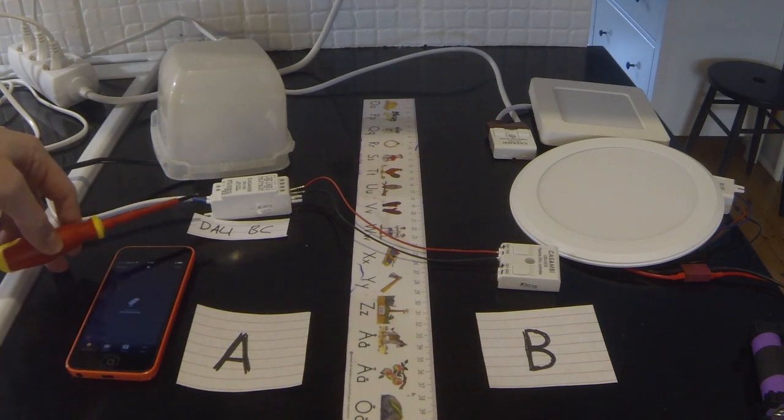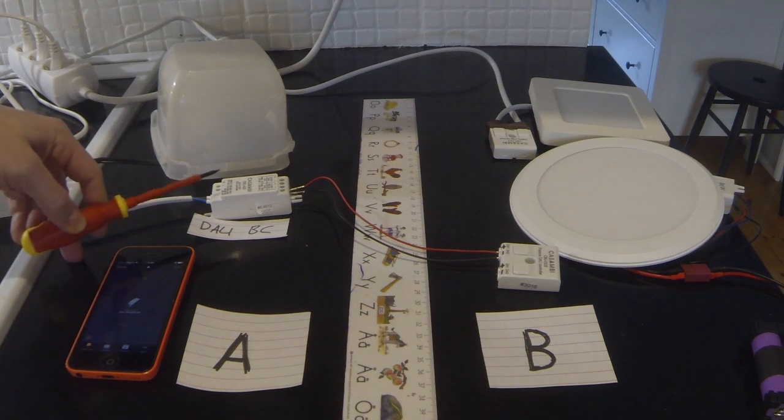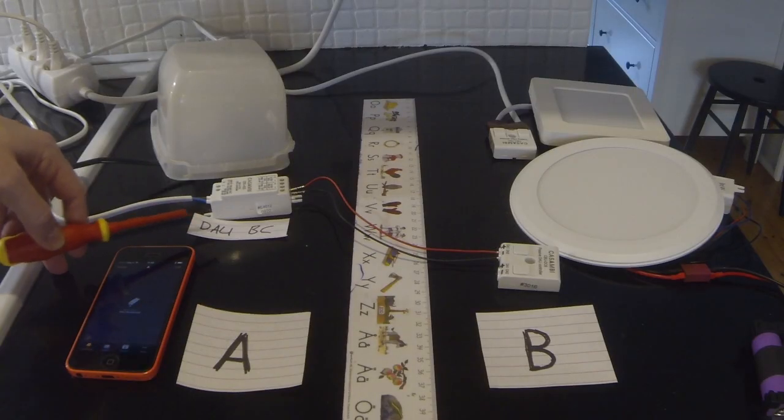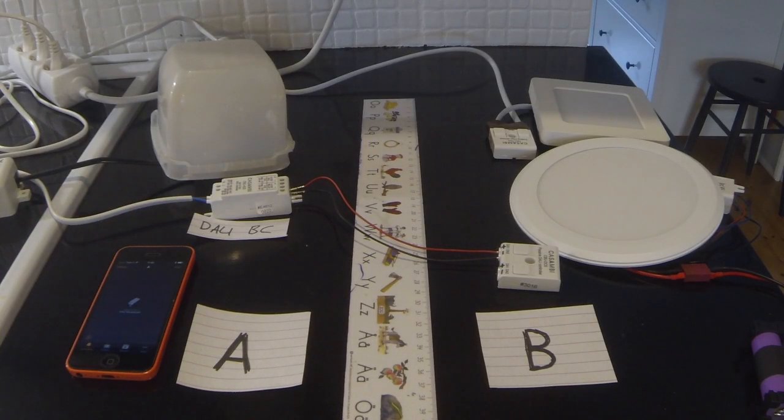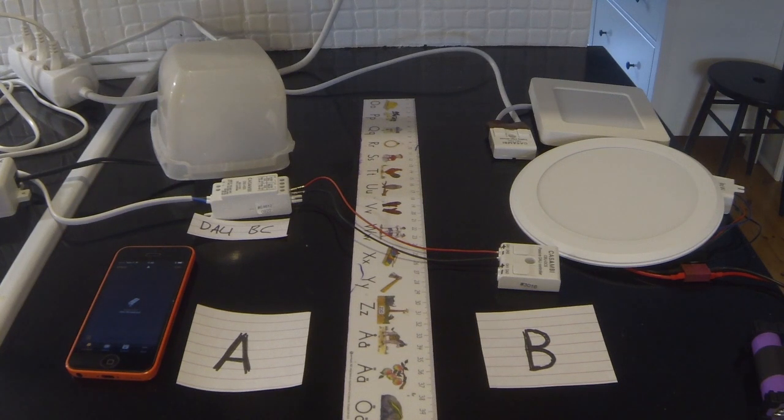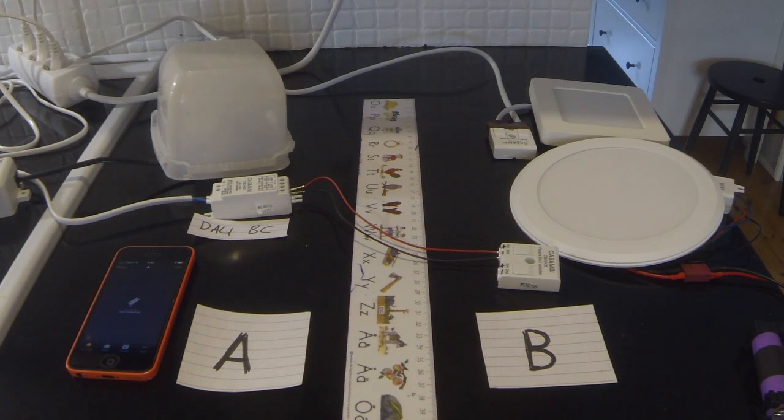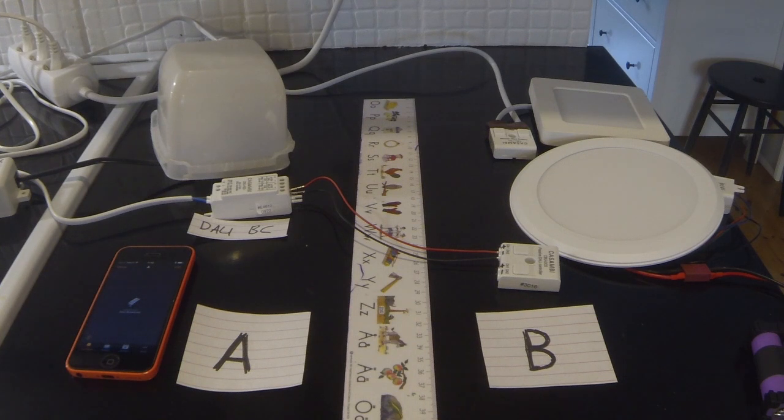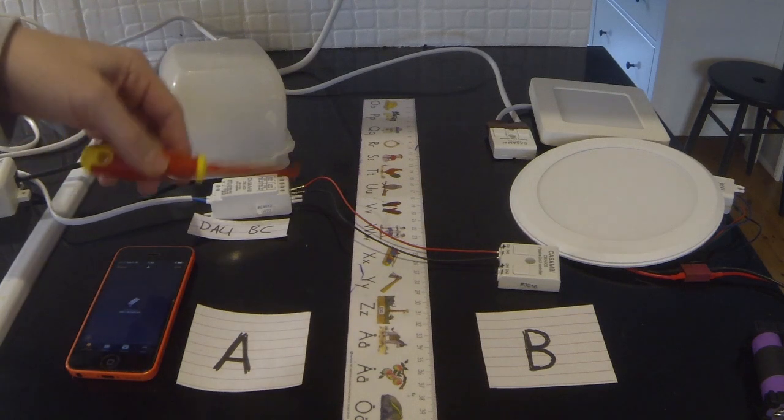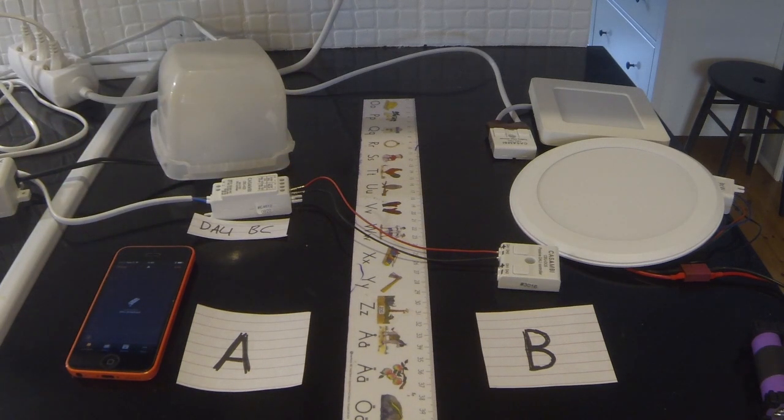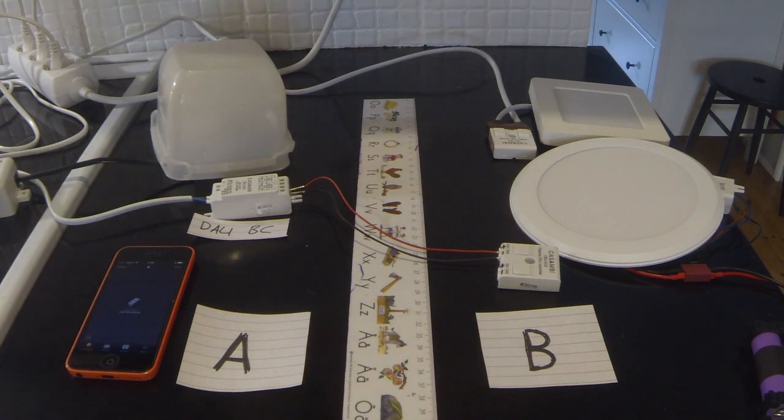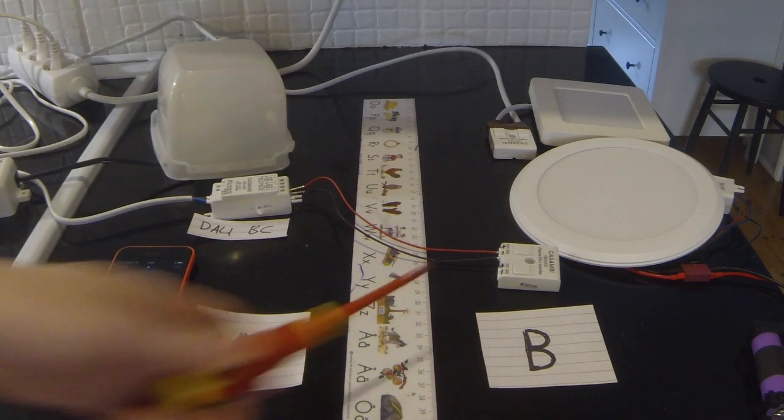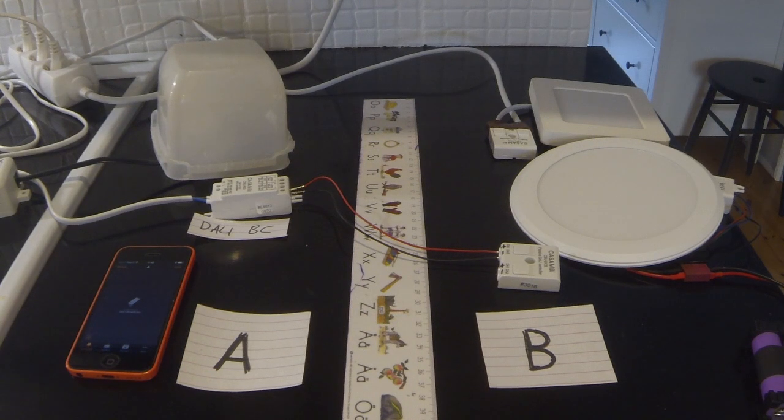So there's a reason why I'm specifically using the CBU A2D. First of all, it's in DALI broadcast mode. Many of you won't really know what DALI is all about. It's essentially a lighting control system, which is wired based. Broadcast is a way of sending out DALI commands which don't require any kind of acknowledgement. So the device sends the command via the wires. And whatever is on the receiving end, this device here in this case, it's expected to just do its job.